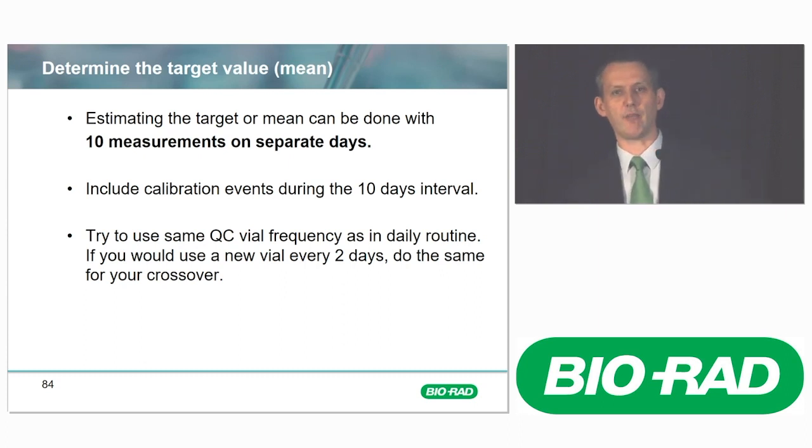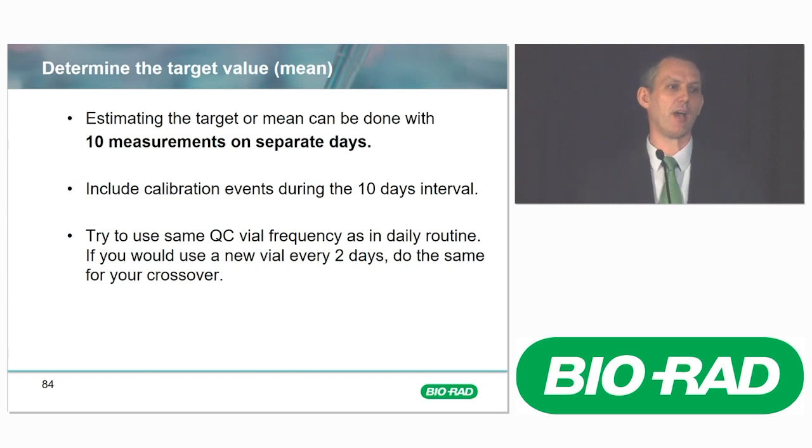We all know that if you use liquid material, the variation of your QC is less than if you use lyophilized material, because then you have a reconstitution, and that also adds to the variation of every individual vial. So if you use lyophilized materials, it's interesting to make sure you have a couple of vial changes also in that crossover study.